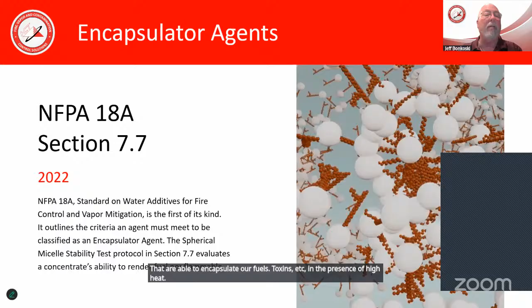If we are looking for a true encapsulator agent that meets NFPA 18A, we need to go to Section 7.7, the qualification test for an encapsulator agent. It's basically a spherical micelle stability test. We want to test to make sure we have stable spherical micelles that are able to encapsulate our fuels, toxins, etc., in the presence of high heat. If we can't, then we're truly not an NFPA 18A encapsulator agent.